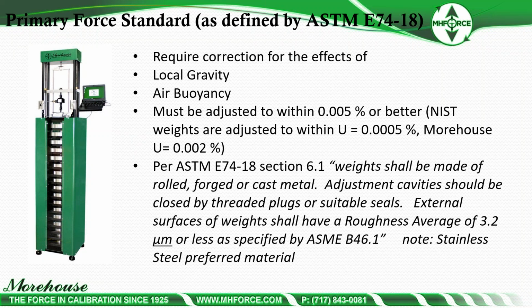The local gravity adjustment, the best thing you can do is have the local gravity surveyed. In the end, what you're going to do is adjust to the local gravity, air buoyancy, everything else, and you're going to realize at our location it's something like 1,000.7 pounds equals 1,000 pounds of force. And then we're going to also make adjustments based on height. And we're going to do lots of different things in that, but just a general overview is what is a primary standard, and that's what it is.